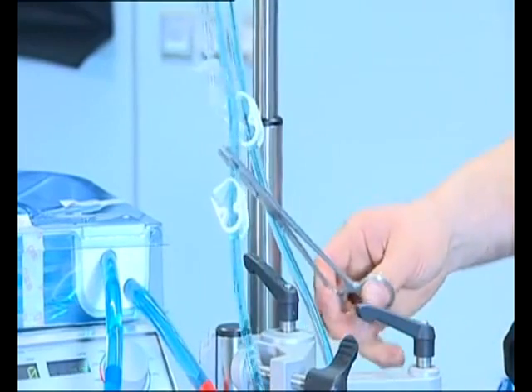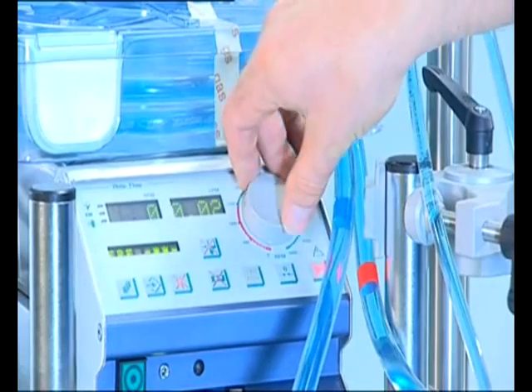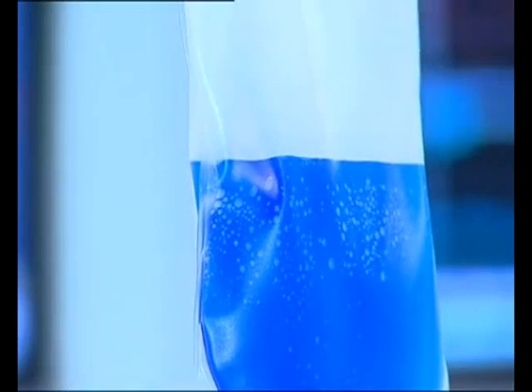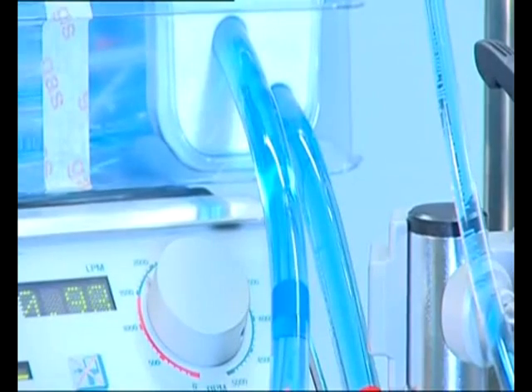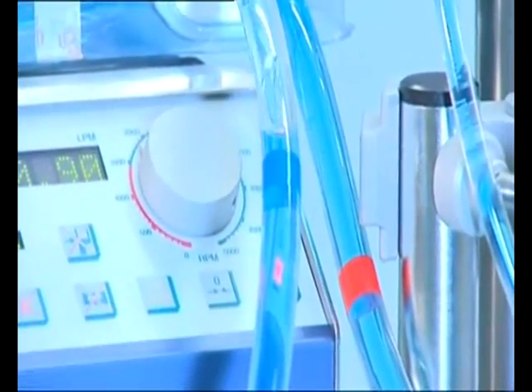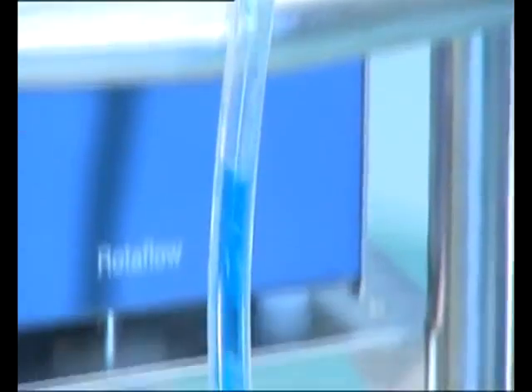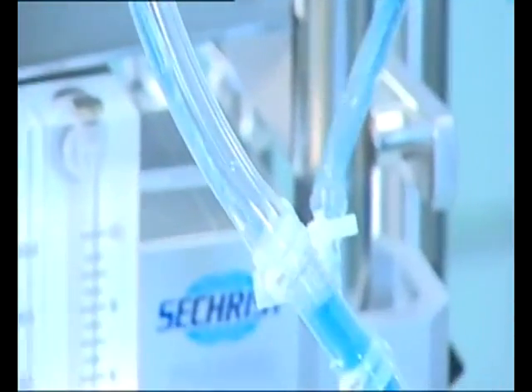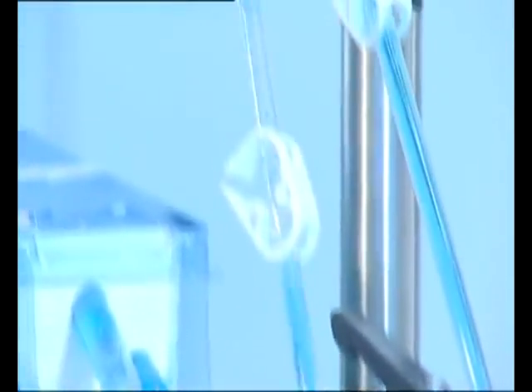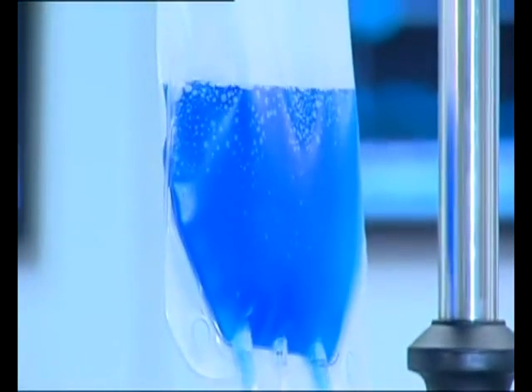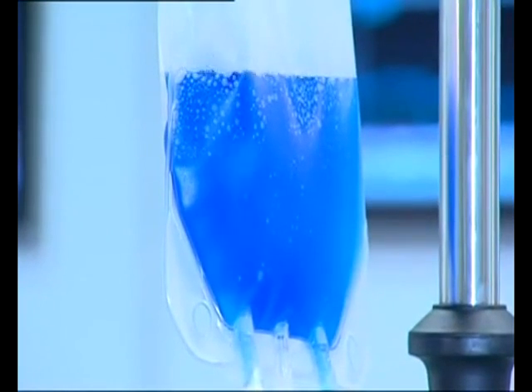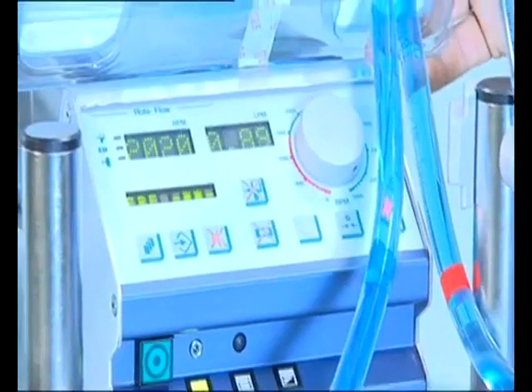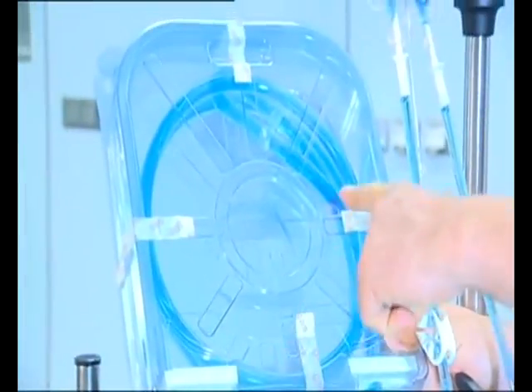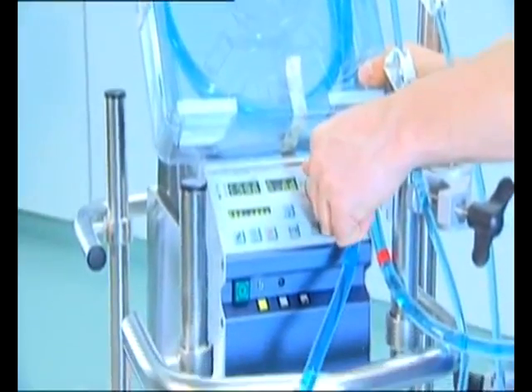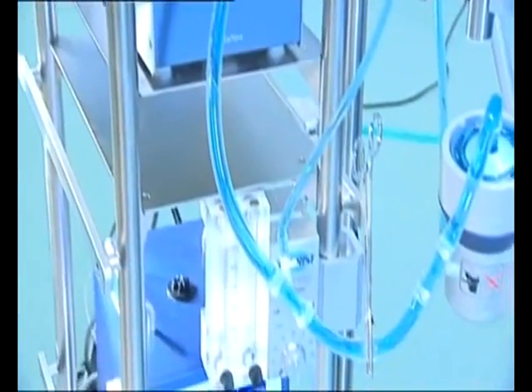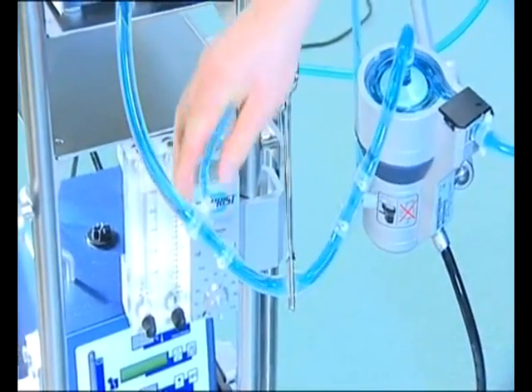The clamps on the priming lines are removed, and the centrifugal pump is restarted. Recirculation now goes through the priming reservoir bag. Any air bubbles in the system are trapped and retained in the bag. When all air bubbles are removed and all lines are bubble-free, the stopcocks on the priming lines are closed and the clamp between the two connectors is removed.